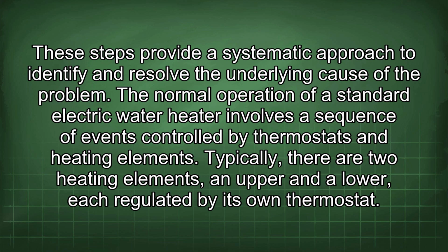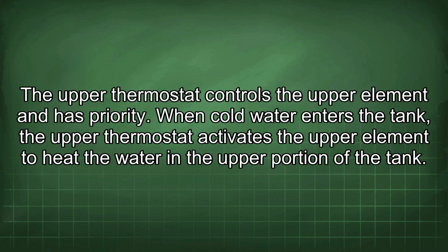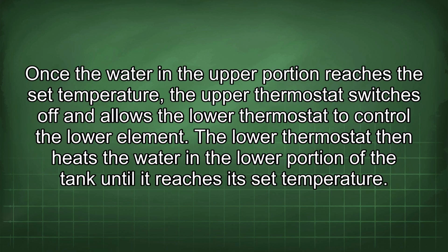The normal operation of a standard electric water heater involves a sequence of events controlled by thermostats and heating elements. Typically, there are two heating elements, an upper and a lower, each regulated by its own thermostat. The upper thermostat controls the upper element and has priority. When cold water enters the tank, the upper thermostat activates the upper element to heat the water in the upper portion of the tank. Once the water in the upper portion reaches the set temperature, the upper thermostat switches off and allows the lower thermostat to control the lower element.